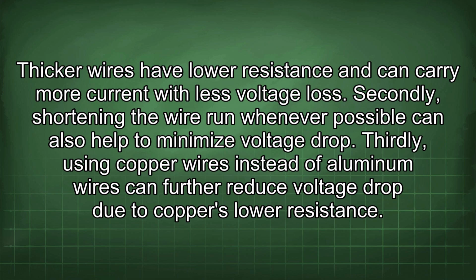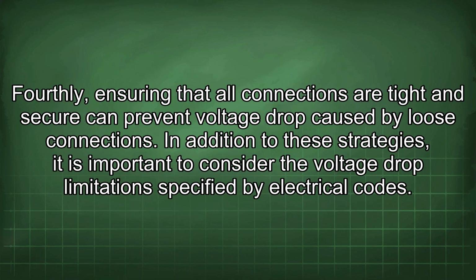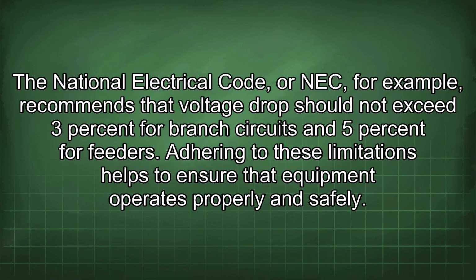Thirdly, using copper wires instead of aluminum wires can further reduce voltage drop due to copper's lower resistance. Fourthly, ensuring that all connections are tight and secure can prevent voltage drop caused by loose connections. In addition to these strategies, it is important to consider the voltage drop limitations specified by electrical codes. The National Electrical Code, or NEC, for example, recommends that voltage drop should not exceed 3% for branch circuits and 5% for feeders. Adhering to these limitations helps to ensure that equipment operates properly and safely.